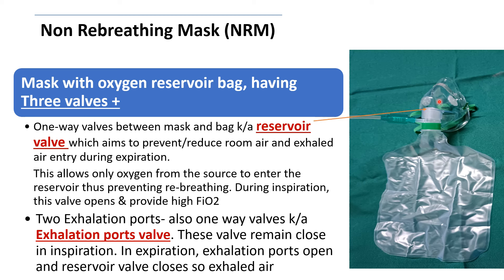This reservoir valve is a one-way valve that closes during exhalation. When the patient exhales, this valve closes so that room air and exhaled air will not enter into the reservoir bag. This valve opens during inspiration so that oxygen enters the mask and the patient can inhale it.